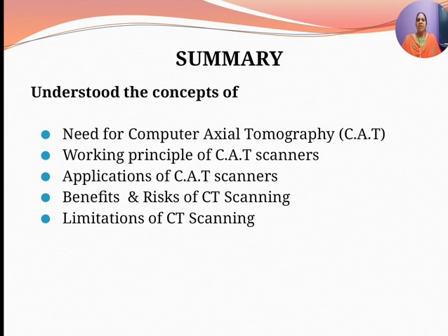The principle of the CT scanner is that a finely collimated source of X-rays is made to pass through a slice of an object or a patient from a variety of directions. The patient is viewed from different angles and two-dimensional pictures can be obtained. The determination of the attenuation characteristics for each small volume of tissue in the patient slice constitutes the transmitted radiation intensity, which is recorded for various irradiations. Mathematically reconstructing the detailed structure and displaying the reconstructed image on a video monitor gives the CT image.